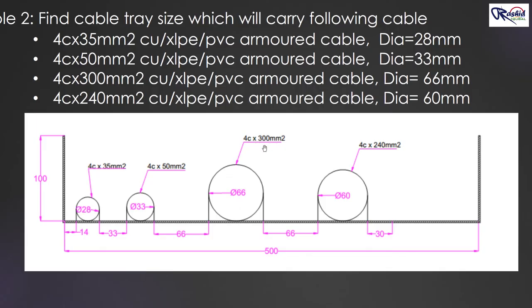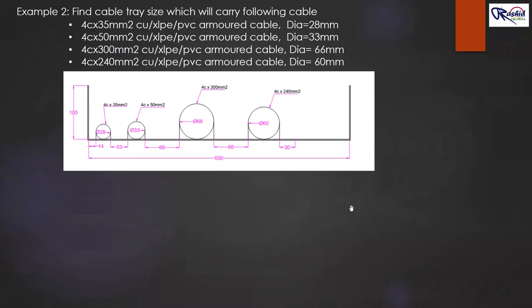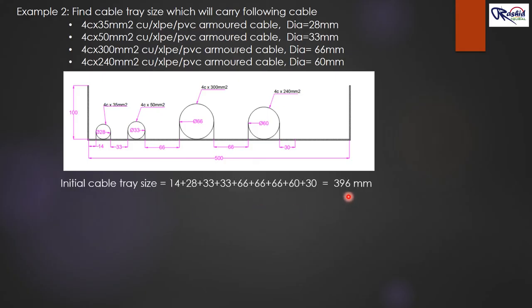For the 4-core 300 mm² and 4-core 240 mm² cables: the bigger cable is still 4-core 300 mm² with diameter 66 mm, so the distance between these two cables is 66 mm. On the right side, the distance between the last cable and the flange is half the diameter of that cable. After all spacing values are summed, the initial cable tray width totals 396 mm.